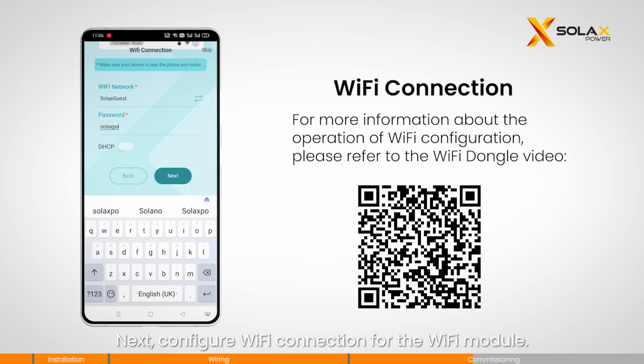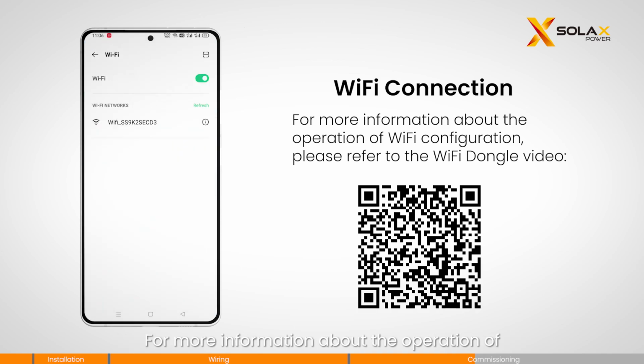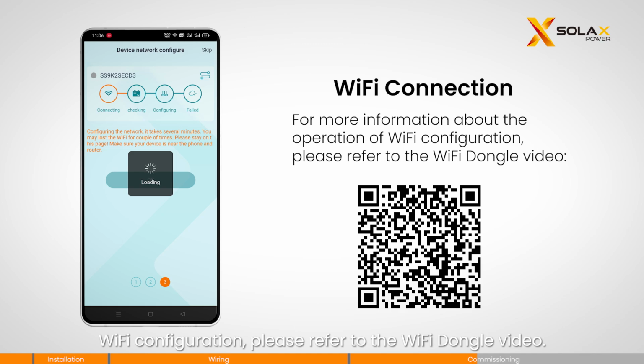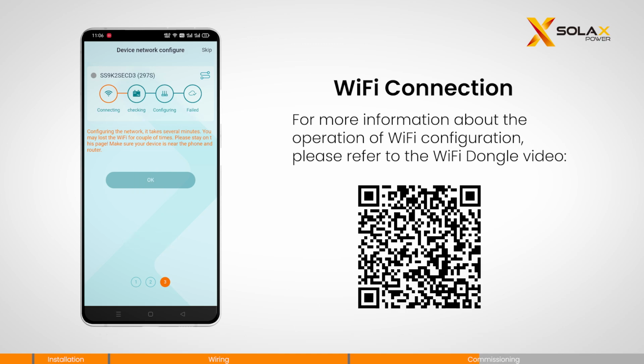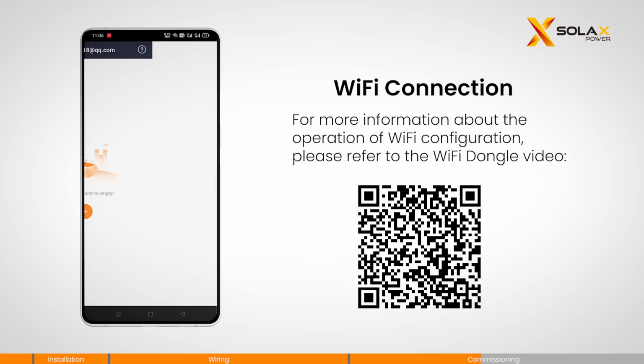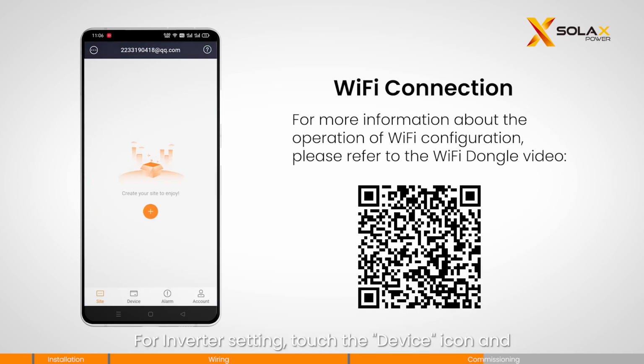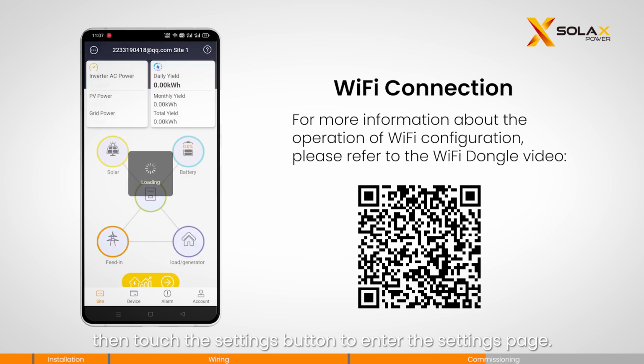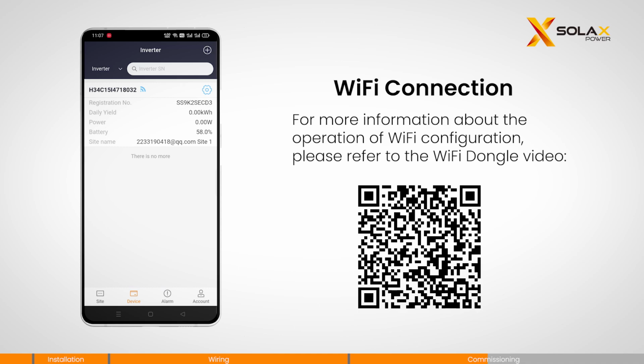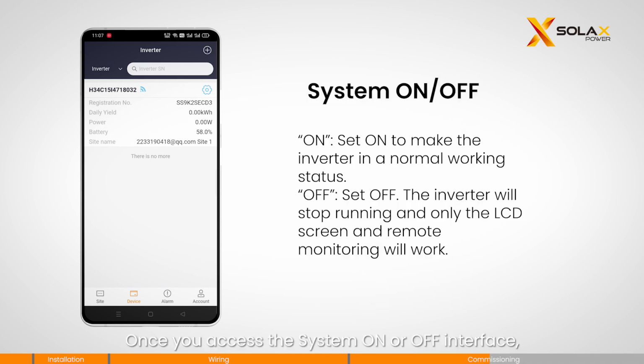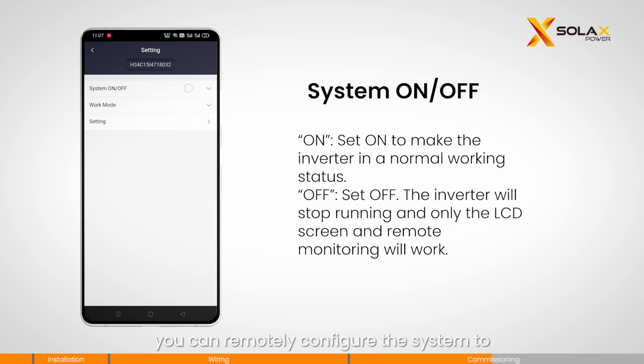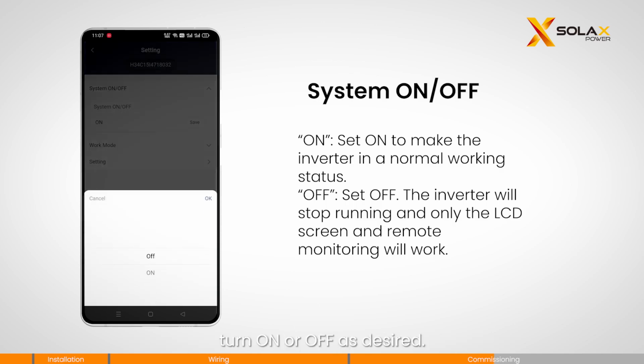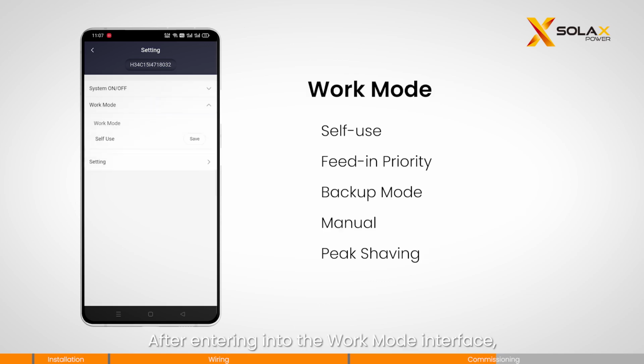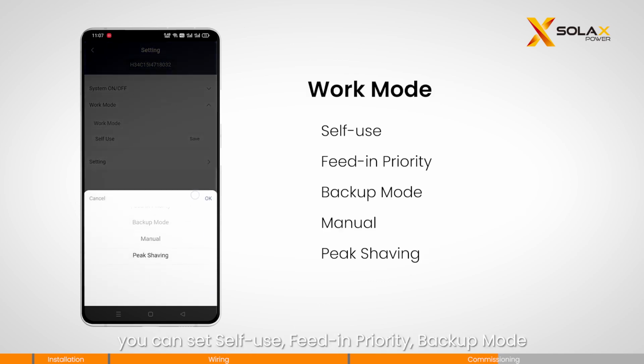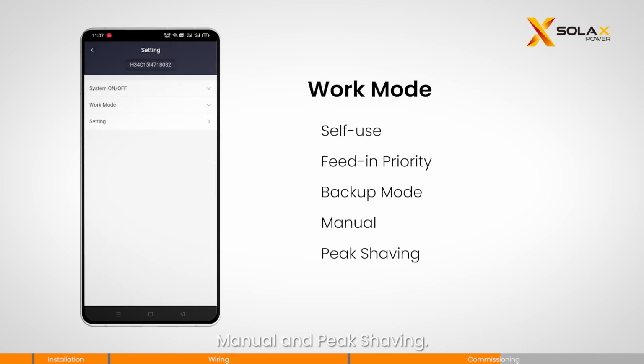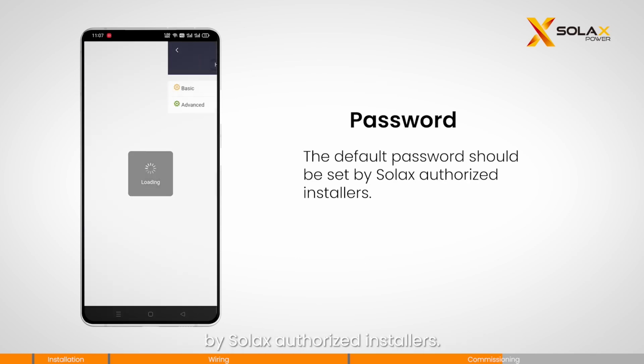Next, configure the Wi-Fi connection for the Wi-Fi module. For more information about the operation of Wi-Fi configuration, please refer to the Wi-Fi dongle video. For inverter setting, touch the device icon and then touch the settings button to enter the settings page. Once you access the System On or OFF interface, you can remotely configure the system to turn on or off as desired. After entering into the Work Mode interface, you can set self-use, feed-in priority, backup mode, manual and peak shaving. The default password should be set by SolaX authorized installers.